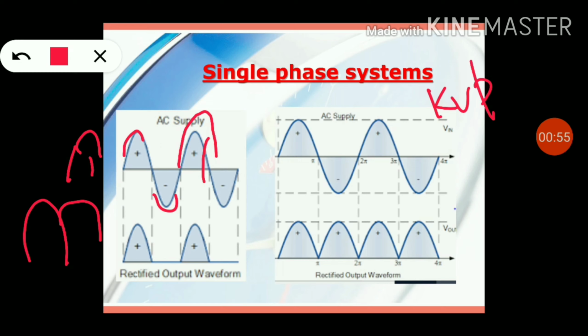Nowadays, even after full rectification, a single phase generator will result in ups and downs in the voltage. As you can see, this is up and down. Because of that, they deliver a varying voltage potential to the X-ray tube, which affects the consistency, amount of radiation and penetration power of radiation during the procedure. So only this portion was usable. Lower energy radiations that are of no use are filtered out.